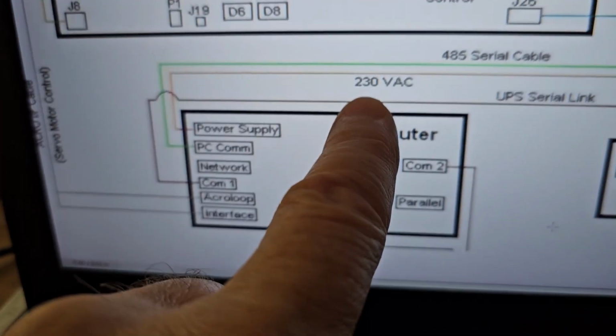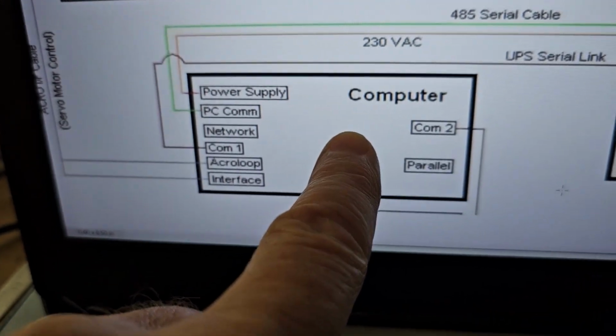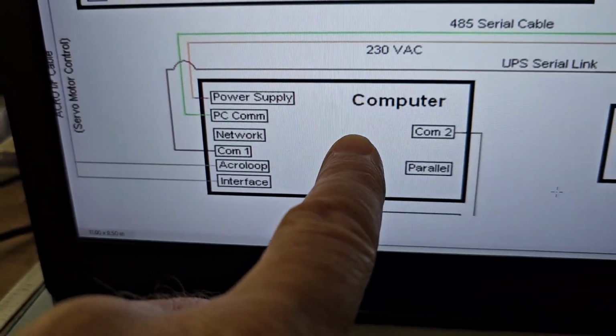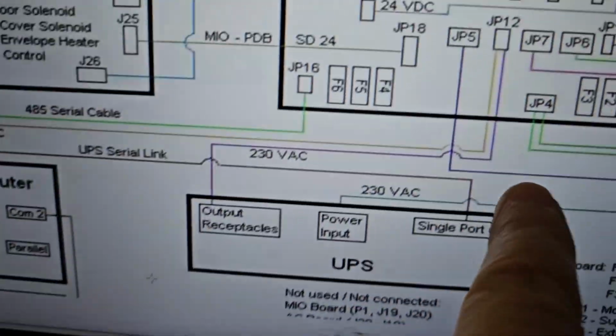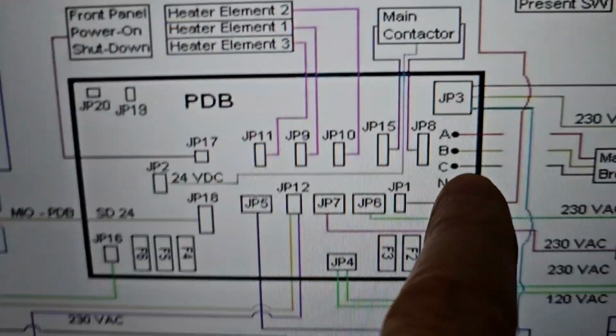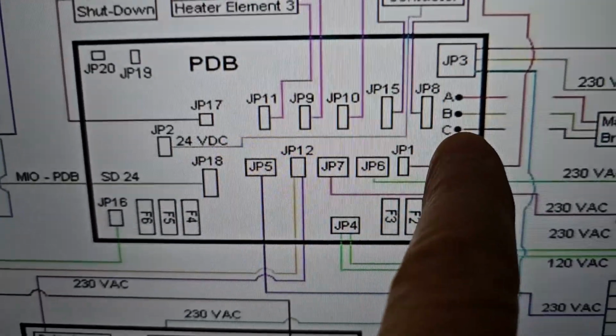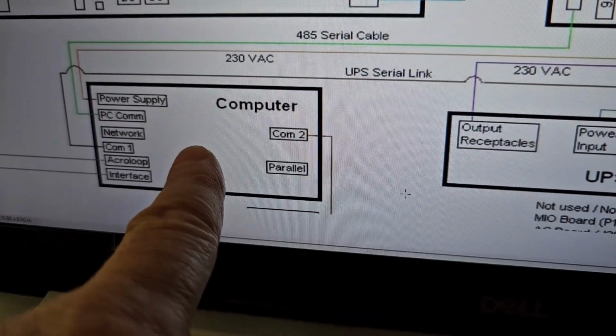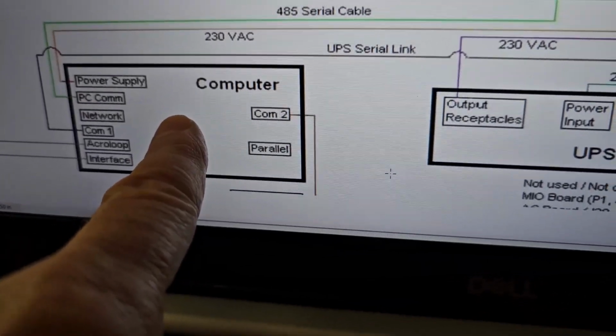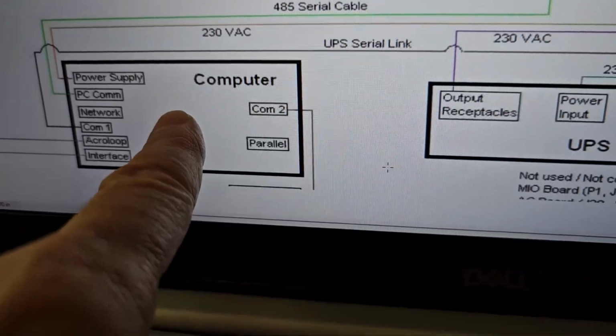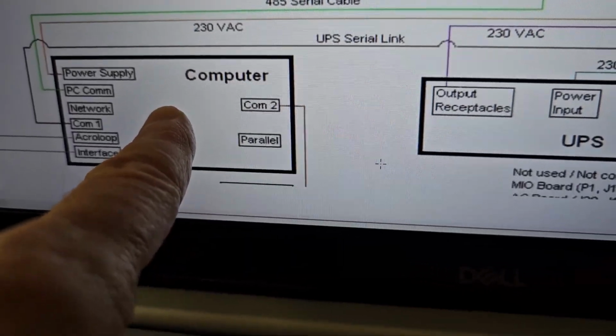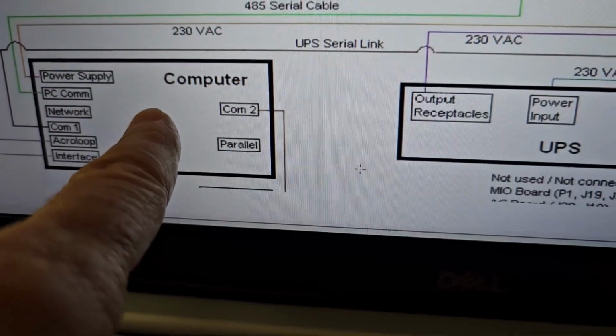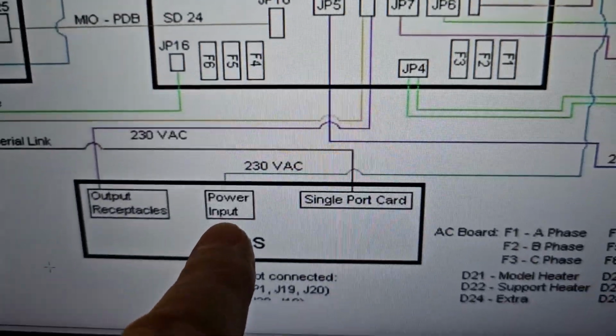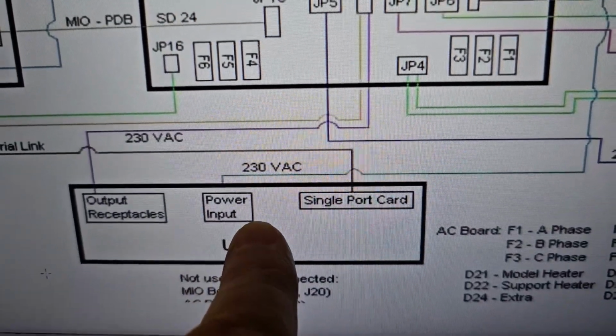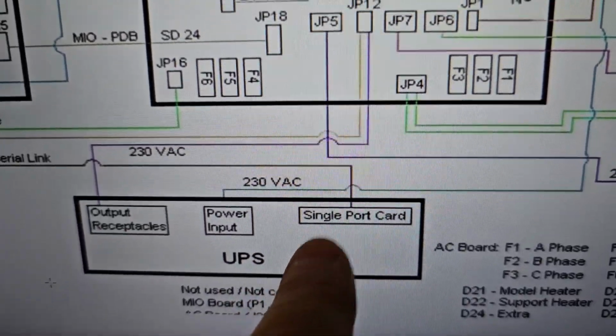This is also 230 volts, single phase, not three phase. That's why I wanted to make sure the manufactured line wasn't feeding the battery or the computer, because the 230 volts coming from the line that goes directly from the sub panel are clean lines. The manufactured line that comes from the three-phase converter motor is the one that's high.